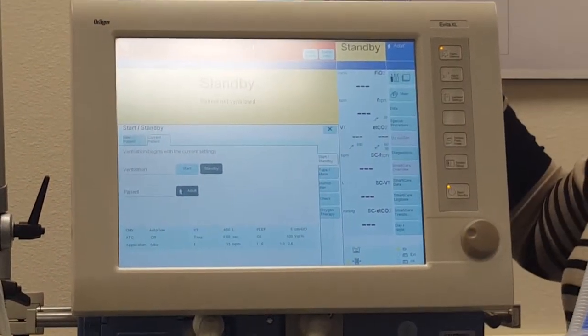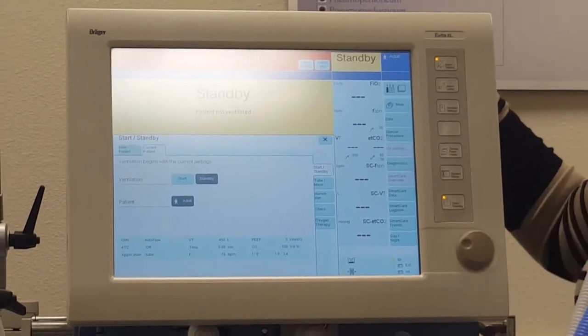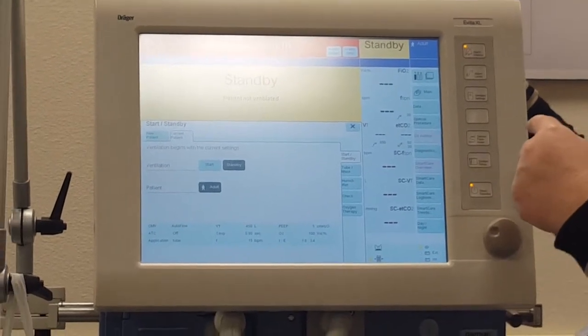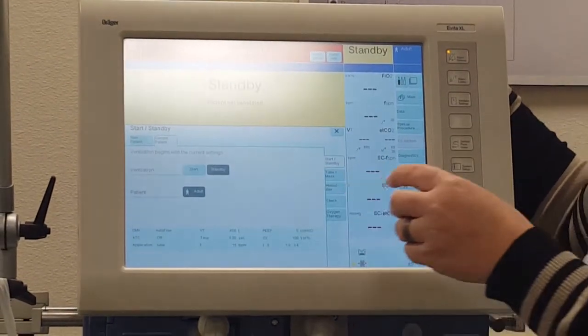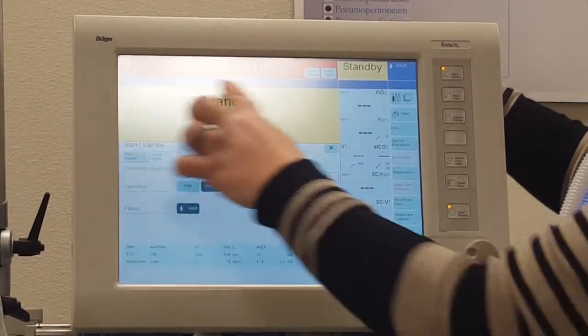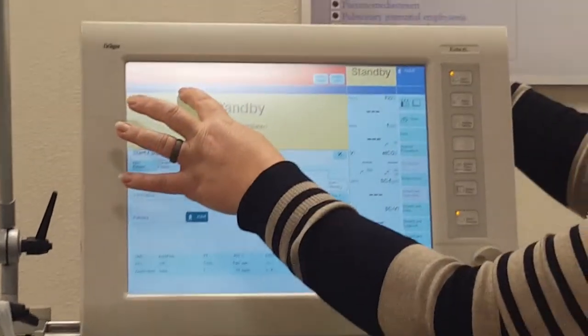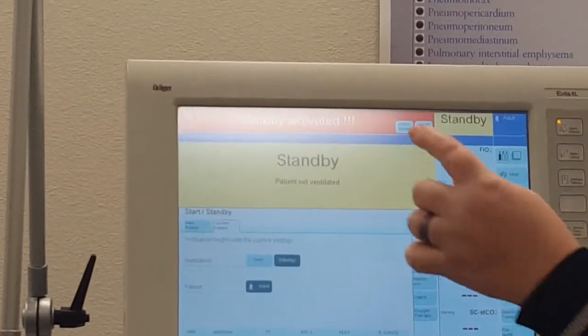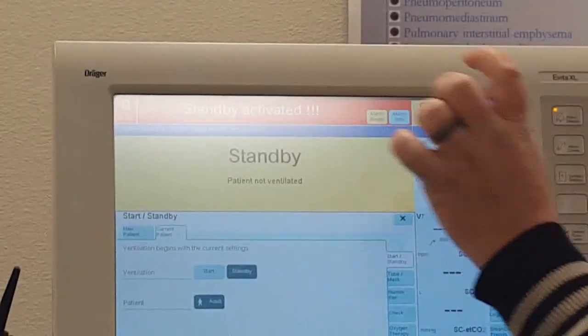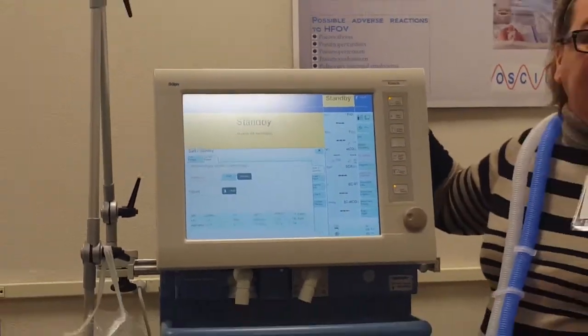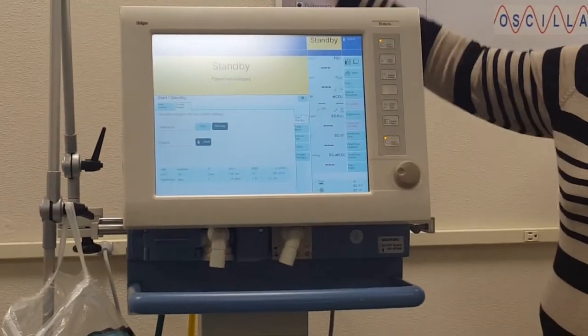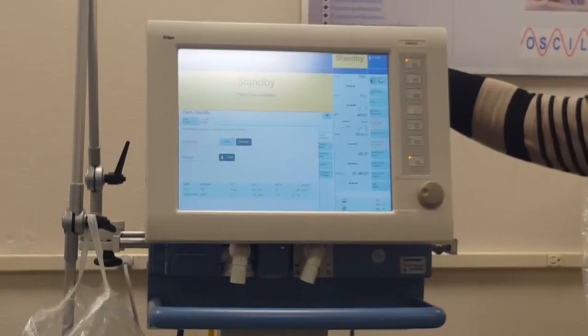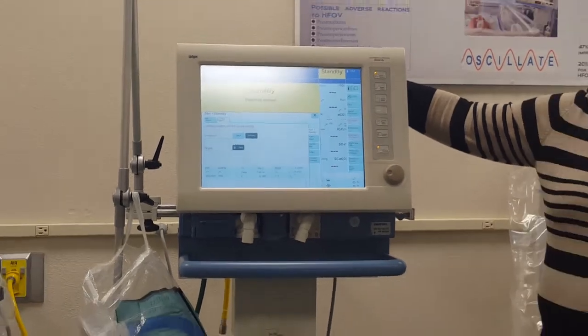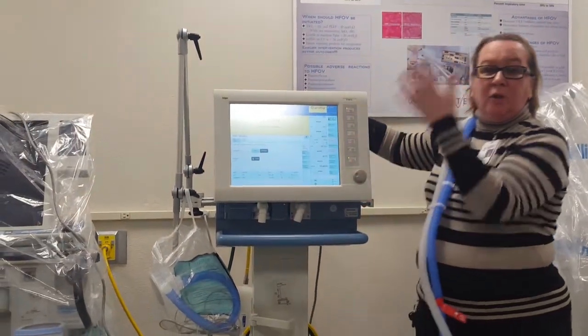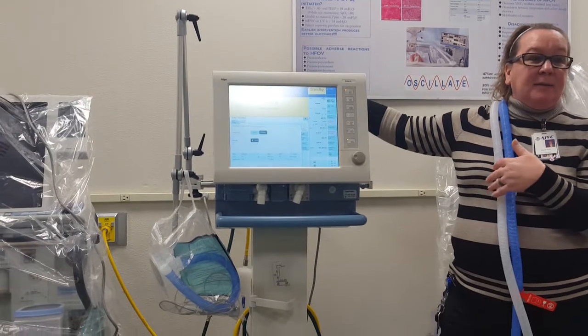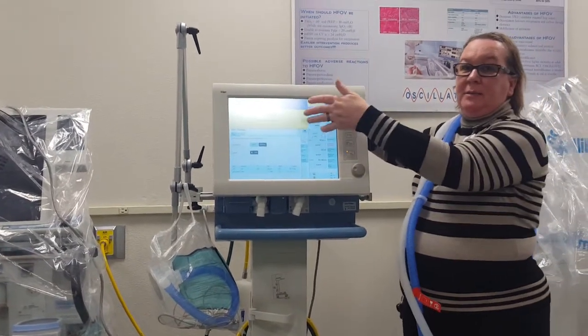This is not standby. This is one of the biggest mistakes on this ventilator. You actually have to do another step to actually put it in standby. Up here in the blue it tells you, confirm standby, touch alarm reset and confirm. So now you push the alarm reset and confirm, and now it's in standby. It should be blue up at the top with nothing else up there. Students tend to just hit standby, confirm, and stop, and then keep going. That's not in standby. It wants to confirm that you really want to be in standby.